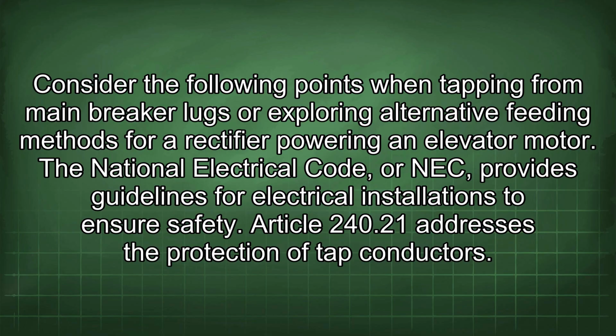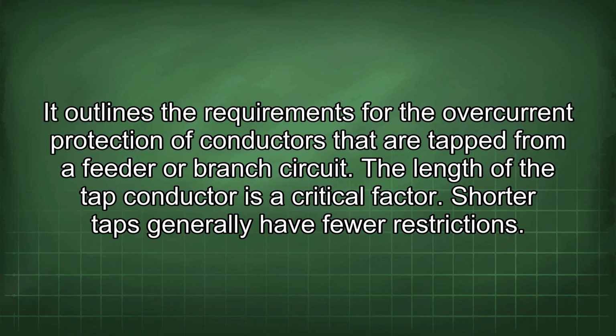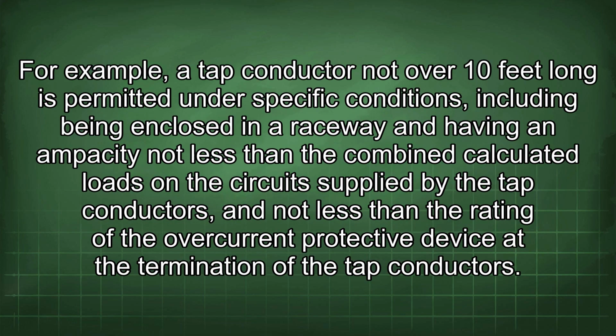Consider the following points when tapping from main breaker lugs or exploring alternative feeding methods for a rectifier powering an elevator motor. The National Electrical Code, or NEC, provides guidelines for electrical installations to ensure safety. Article 240.21 addresses the protection of tap conductors. It outlines the requirements for the overcurrent protection of conductors that are tapped from a feeder or branch circuit. The length of the tap conductor is a critical factor. Shorter taps generally have fewer restrictions. For example, a tap conductor not over 10 feet long is permitted under specific conditions, including being enclosed in a raceway and having an ampacity not less than the combined calculated loads on the circuit supplied by the tap conductors, and not less than the rating of the overcurrent protective device at the termination of the tap conductors.